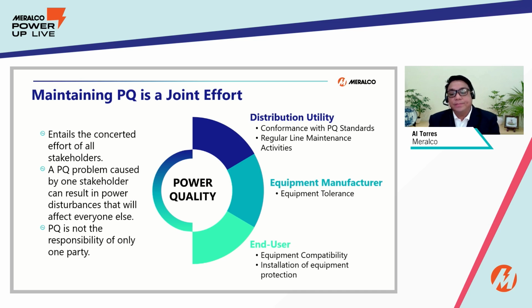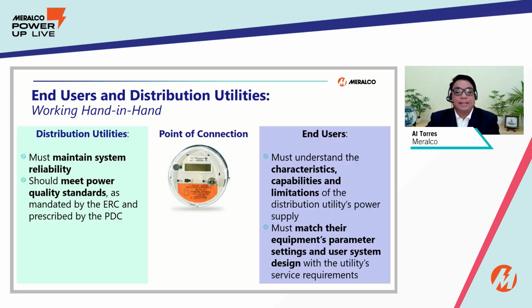For the end user, they must ensure that all the end use equipment are compatible in terms of rating and equipment tolerance. While for the equipment manufacturer, they must conform with the tolerance specified by the standard. Usually kung sa Philippine Distribution Code, plus minus 10%, dapat yung mga equipment manufacturers natin, yung tolerance ng equipment nila, plus minus 10% din. So next slide please.